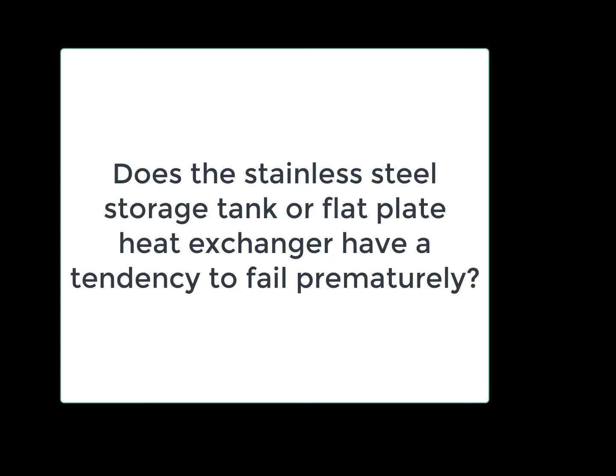Does the customer's stainless steel storage tank or flat plate heat exchanger have a tendency to fail prematurely? This is a consequence of the highway department using chlorides to de-ice the streets. If the home is on a private well and is located anywhere near Interstate 70 or Highway 285 or I-25 or any major thoroughfare that is de-iced using chlorides, the chlorides have basically gotten into the aquifer, and those chlorides are causing chloride stress cracking within the stainless steel storage tank or the stainless steel heat exchanger. You will have to replace the storage tank with a steel glass-lined tank in order to avoid additional failures in the near future. As it pertains to heat exchangers, you will have to use a titanium-based heat exchanger, which is rather expensive. I would consider the alternative of setting a glass-lined steel tank as opposed to trying to find a titanium heat exchanger that can withstand chlorides.